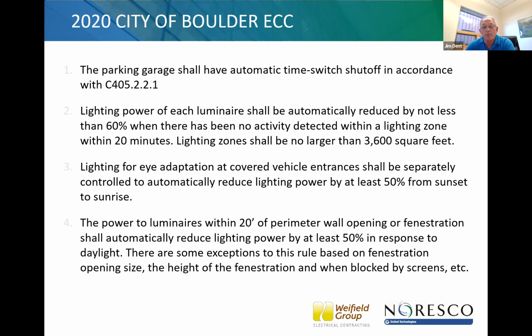And then the power to luminaires within 20 feet of the perimeter wall opening or fenestration shall be automatically reduced by at least 50% in response to daylight. Again, this is in the 2021 IECC. The last two parking garages I've worked on, where I was part of the design team, our lighting power density has been 0.06 watts per square foot. So your payback on this is going to be a long time, but at least we're saving some energy.